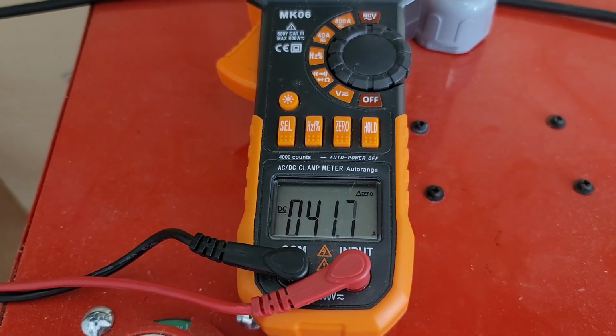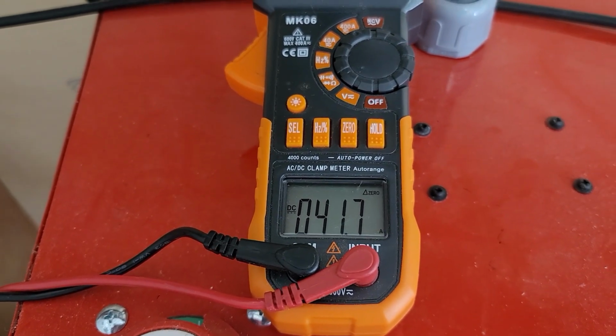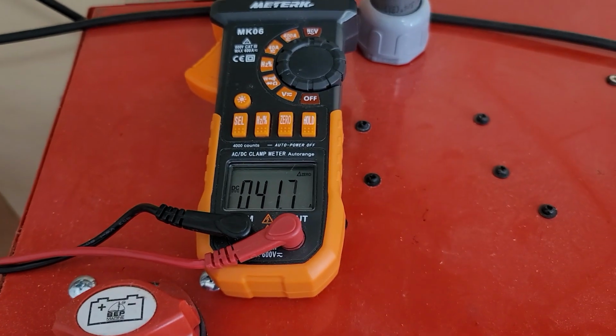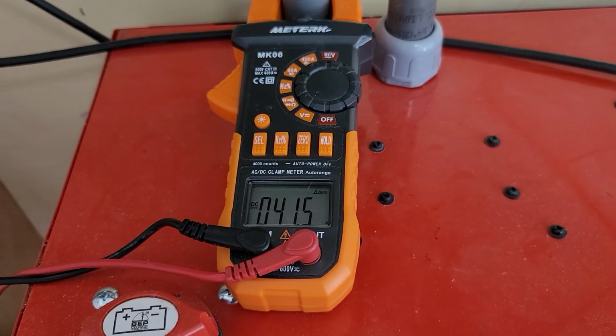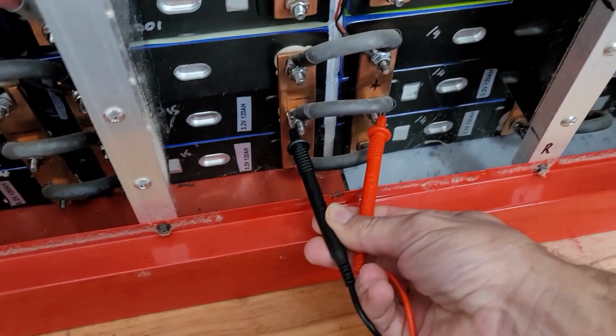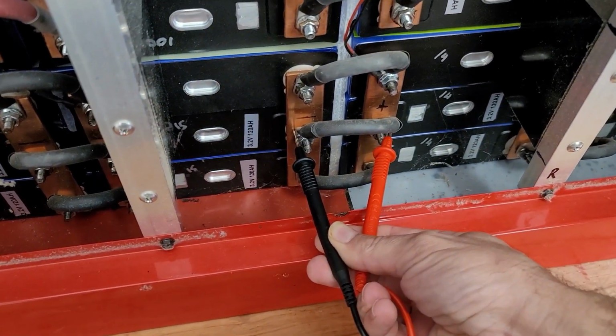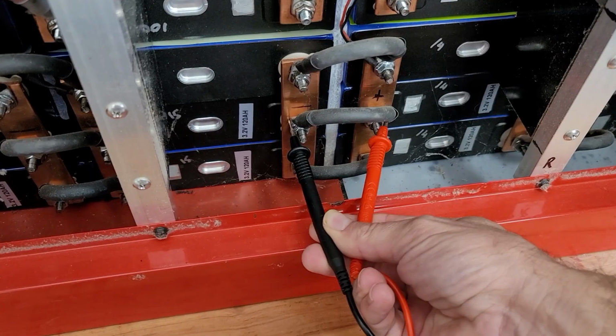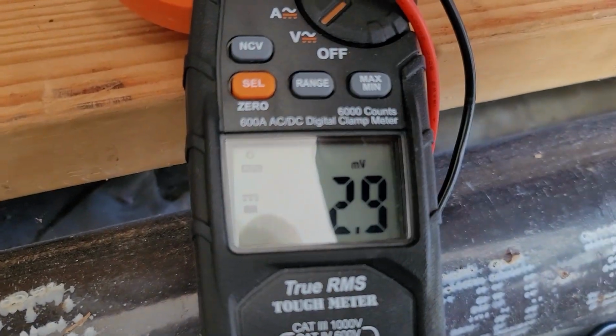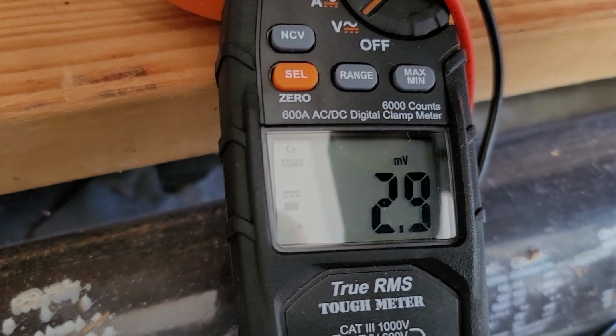Right now we are at a 41.7 amp charge on this Powerwall. Let's see what the voltage drop is going to be. We're at the same connection point between modules 14 and 15, and the voltage drop right now is at 2.9 millivolts.